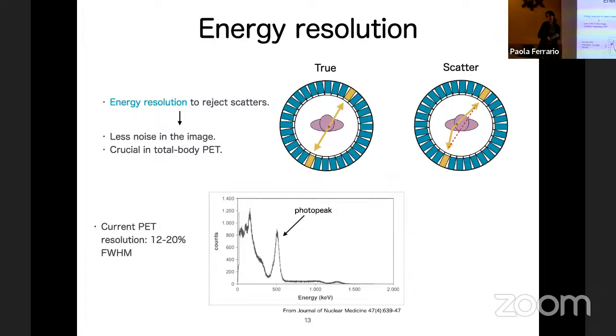Okay, on top of sensitivity, there are other parameters that play a role in PET scanners. One is the energy resolution, which means the precision with which we can measure the energy of the photons that arrive in our detector. Why is that important? The photons have a fixed energy, which is around 511 keV. If you can measure this energy with high precision, you are able to reject some events that produce noise in your image. Which are these events? They are events when one or both of the two gammas interact in the body of the patient before reaching your detectors.